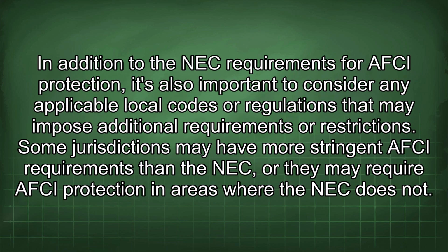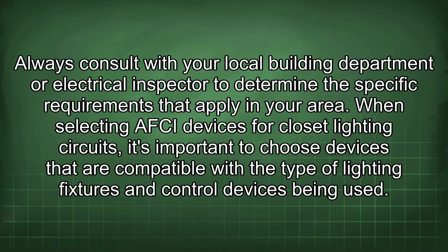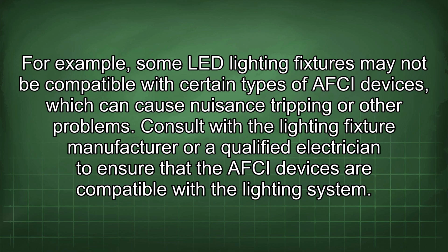In addition to the NEC requirements for AFCI protection, it's also important to consider any applicable local codes or regulations that may impose additional requirements or restrictions. Some jurisdictions may have more stringent AFCI requirements than the NEC, or they may require AFCI protection in areas where the NEC does not. Always consult with your local building department or electrical inspector to determine the specific requirements that apply in your area. When selecting AFCI devices for closet lighting circuits, it's important to choose devices that are compatible with the type of lighting fixtures and control devices being used. For example, some LED lighting fixtures may not be compatible with certain types of AFCI devices, which can cause nuisance tripping or other problems.